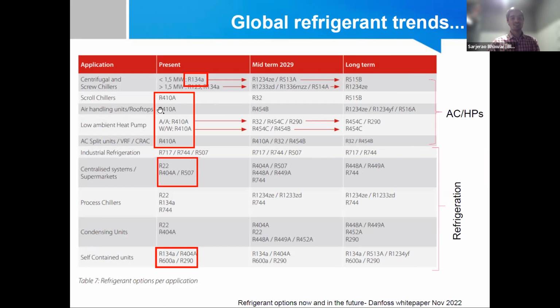Scroll chillers, air handling units, low temperature heat pumps, ACs, VRFs, and central air conditioning systems are more dominated by R410A systems currently. But as regulations come in, in the near future we are moving towards R32, R454B, or in some cases R454C. Long-term, the industry is looking at refrigerants predominantly moving towards HFOs, HFO blends, or R32, and in some cases R290. That's the ACs and heat pump scenario.